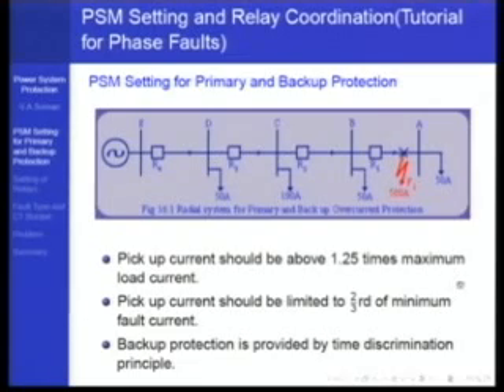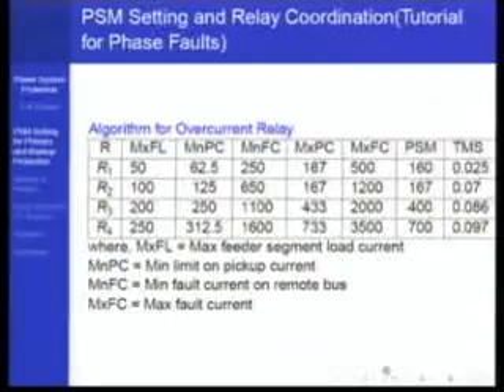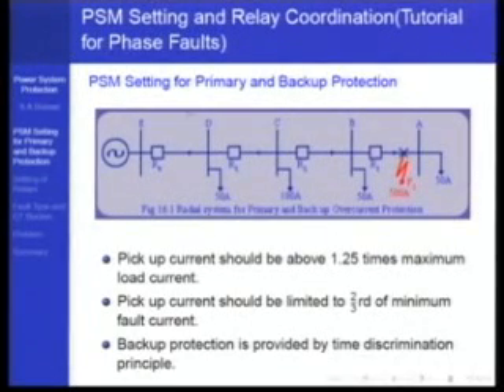And the backup protection is provided by the time discrimination principle. So for this system, this is the maximum feeder segment load current, MXFL, the full load current maximum value. Relay R1 sees a maximum load current of 50 amperes. Relay R2 sees a maximum load current of 100 amperes. 50 plus 50 will flow through this 100.